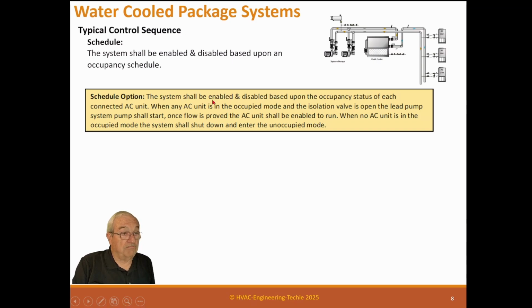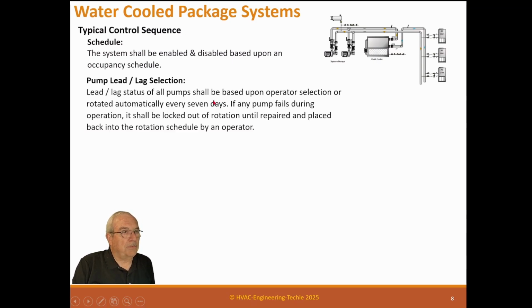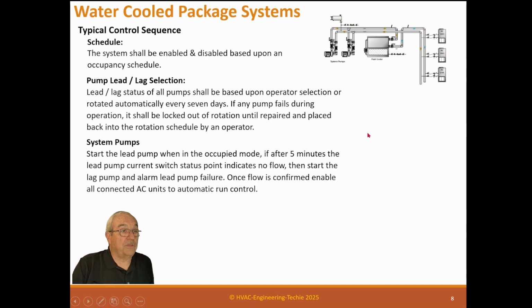It just says that if no one pushes an override button, now on a hard schedule, if you have override buttons, then you have that switch the central plant to occupied mode is all. Pump lead lag status, since we've got staged pumps, one handles the system, one's a standby. Lead lag status of all pumps shall be based upon operator selection or rotated automatically every 7 days. If any pump fails during operation, it shall be locked out of rotation until repaired and placed back into rotation by an operator. So in other words, an operator needs to say this pump's ready to run before it is placed back in rotation.